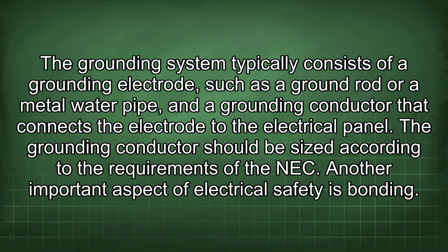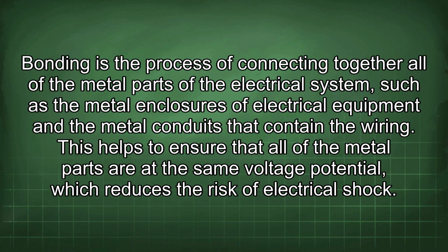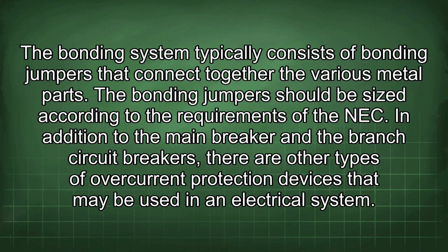Another important aspect of electrical safety is bonding. Bonding is the process of connecting together all of the metal parts of the electrical system, such as the metal enclosures of electrical equipment and the metal conduits that contain the wiring. This helps to ensure that all of the metal parts are at the same voltage potential, which reduces the risk of electrical shock. The bonding system typically consists of bonding jumpers that connect together the various metal parts. The bonding jumpers should be sized according to the requirements of the NEC.